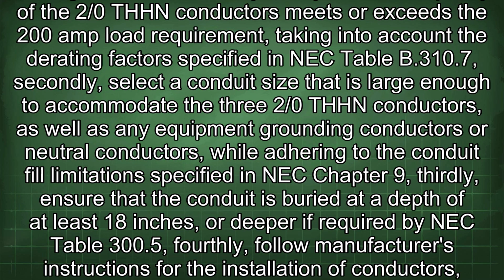Here's a summary of the key considerations when using 2/0 THHN conductors for a 200 amp underground service. Firstly, verify that the ampacity of the 2/0 THHN conductors meets or exceeds the 200 amp load requirement, taking into account the derating factors specified in NEC Table B.310.7. Secondly, select a conduit size that is large enough to accommodate the 3 2/0 THHN conductors, as well as any equipment grounding conductors or neutral conductors, while adhering to the conduit fill limitations specified in NEC Chapter 9.